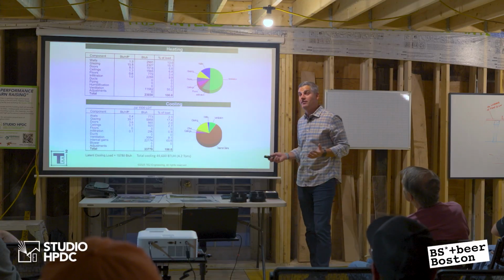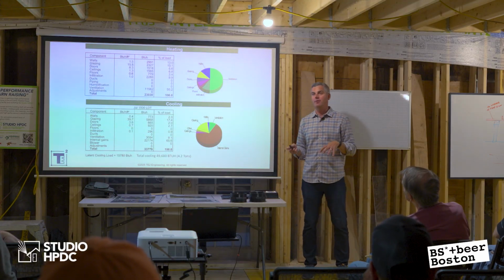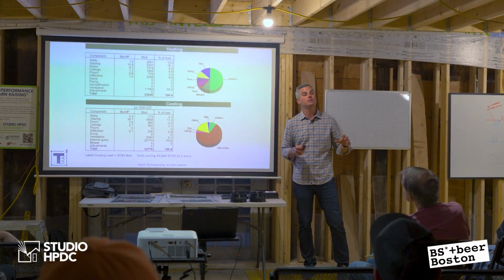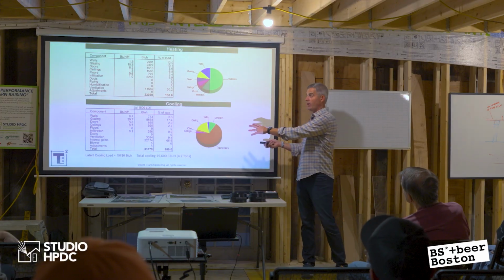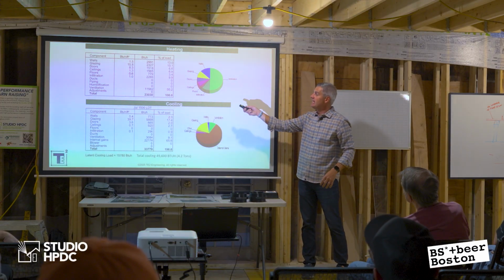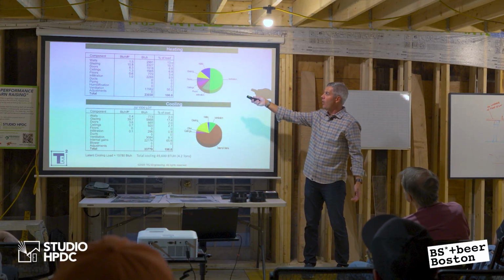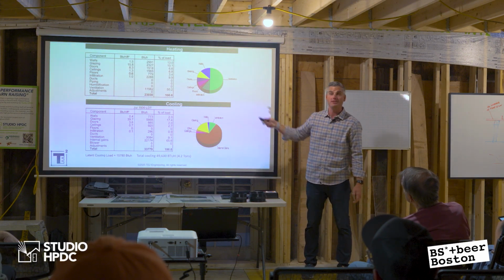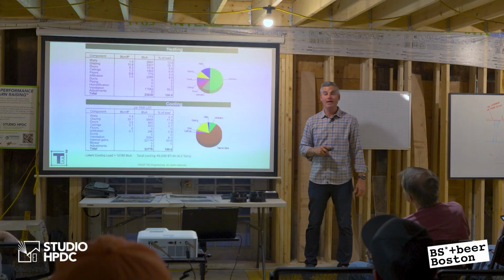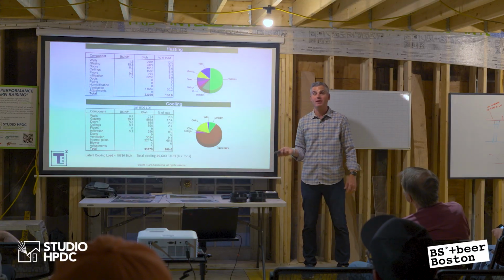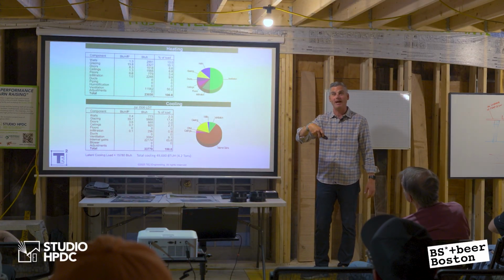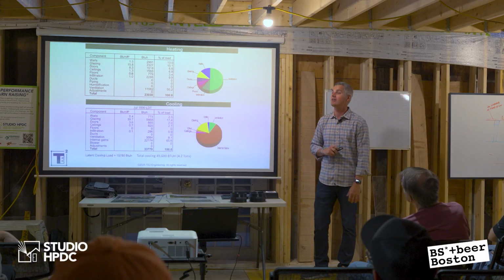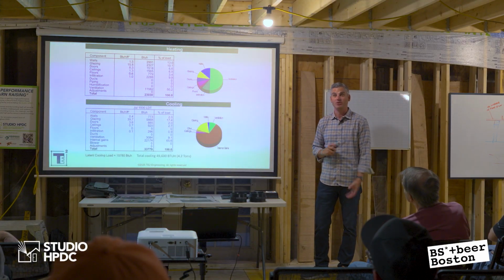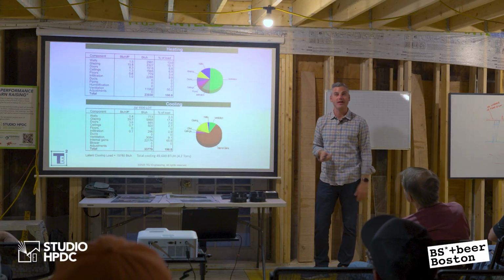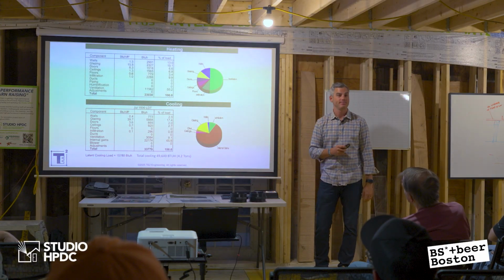But this is the reality of it, that this type of building in a highly occupied space is very different than a house. And the math tells us why, right? Same thing in the heating months. The building enclosure is actually really good. It's unbelievable. The ventilation load represents 50%. And you can make the argument that the heating load is actually going to be less, because if I have 55 people in here in the wintertime, we're going to be giving off heat. The heating system isn't going to run as much. So it net helps us in the wintertime, but it hurts us in the summertime.